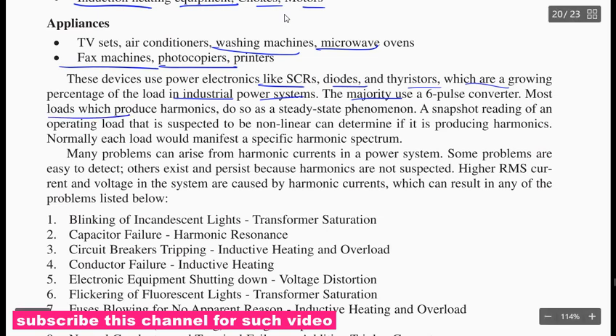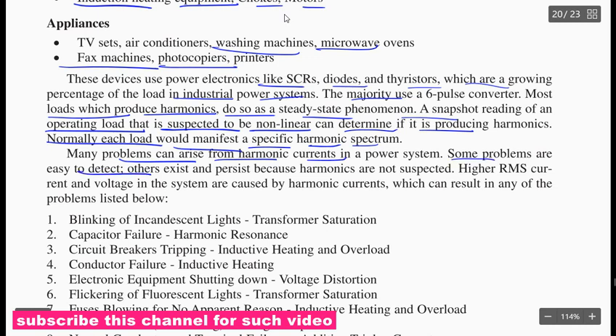Most loads which produce harmonics do so as a steady state phenomenon, and a snapshot reading of the operating load that is suspected to be nonlinear can determine whether it is producing harmonics normally. Each load would manifest a specific harmonics spectrum. Many problems can arise from harmonic current in the power system. Some problems are easy to detect and others persist because harmonics are not suspected.